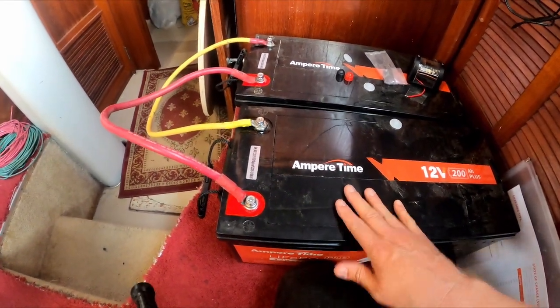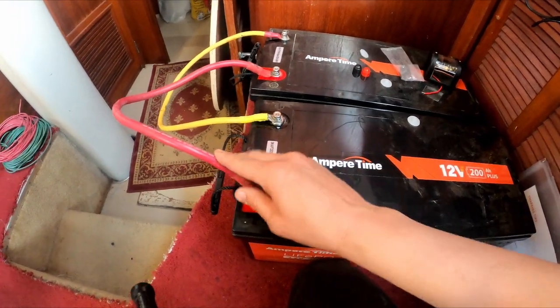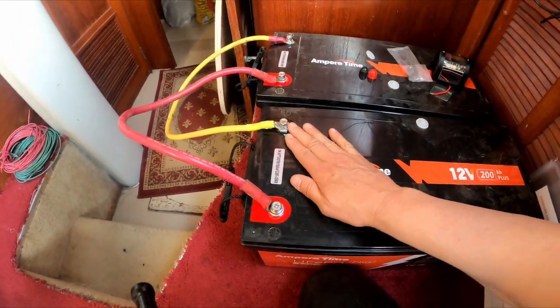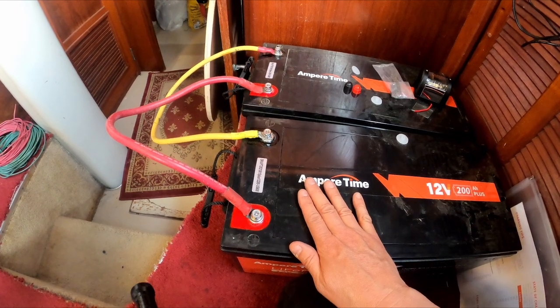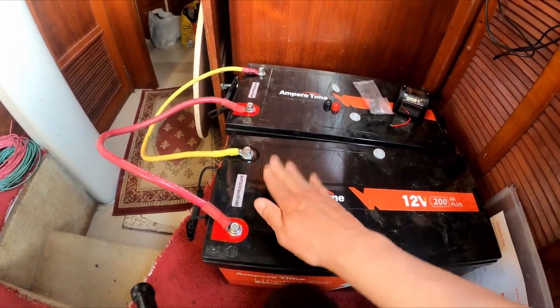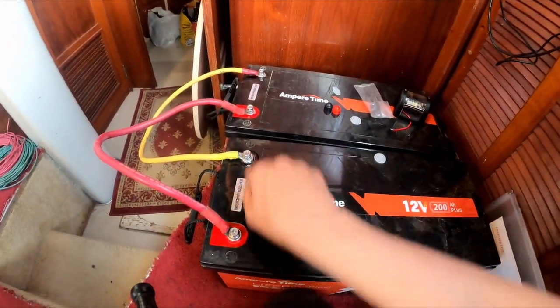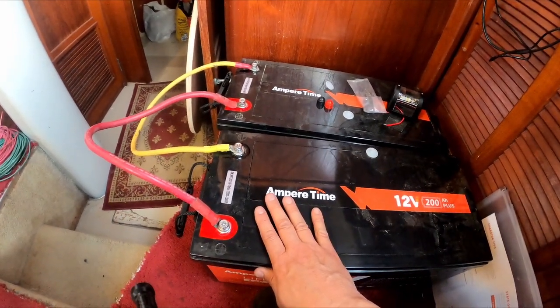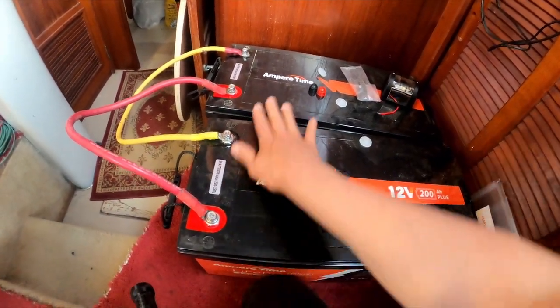At this point, we have both batteries connected in parallel, plus to plus, minus to minus, so that the 2 batteries can equalize each other. We'll let them rest for 12 hours, then check the voltages on each battery, disconnect, and check the voltages on each battery and the voltages together.